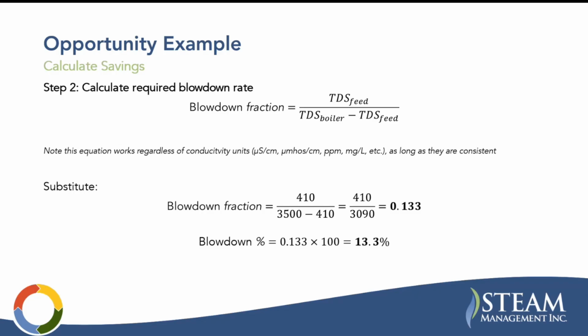Remember, I mentioned that typical is 2 to 5%. So 13.3% is pretty high. I think the highest I've ever seen is 19% at a chemical plant once. But this is a high blowdown flow. So even though we have a low steam flow, we're blowing out 13.3% of our boiler feed water. We're blowing it down the drain.